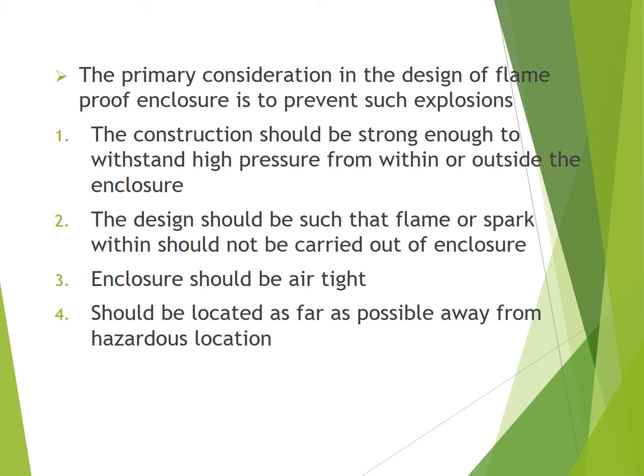Primary consideration: the design of flame-proof enclosure. If we want to operate equipment in this hazardous zone, where a flammable atmosphere is present, any spark created can cause a fire. To avoid that, we have to consider a flame-proof enclosure. The construction should be strong enough to withstand high pressure from within the enclosure, and the design should be such that the flame or spark within should not come out. If the spark inside the equipment comes out and comes in contact with the flammable hazardous atmosphere, then it can catch fire. We have to avoid that type of situation, so we use flame-proof apparatus. The design considerations for flame-proof apparatus are like this.